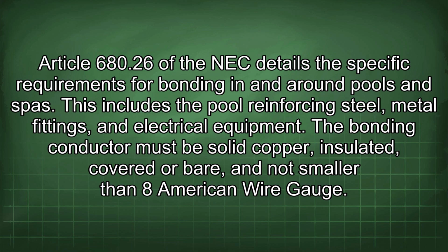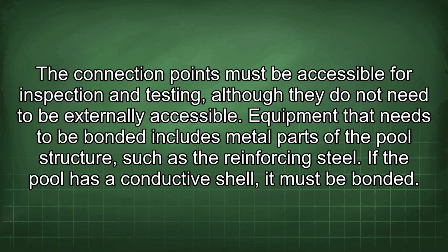680.26 of the NEC details the specific requirements for bonding in and around pools and spas. This includes the pool reinforcing steel, metal fittings, and electrical equipment. The bonding conductor must be solid copper, insulated, covered or bare, and not smaller than 8 American wire gauge. The connection points must be accessible for inspection and testing, although they do not need to be externally accessible.